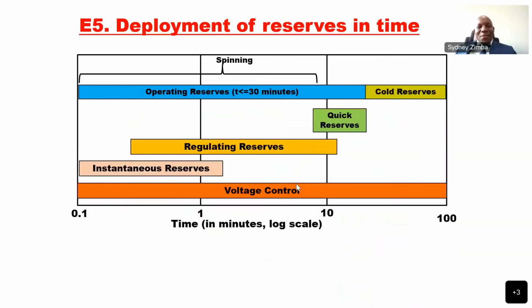So talking about the reserves, how are they deployed? In time, the instantaneous one is in milliseconds. An event happens quickly, we want to respond and correct the discrepancy. Then after milliseconds, close to a minute, the regulating reserves come in. At that time, the instantaneous reserves are released to get them set for the next disturbance. Then those quick reserves which are offline can now be synchronized. So all these up to quick reserves are operating reserves. Then going forward, after 10 minutes or so, we dispatch the cold reserves through market arrangements, or we run the generators which were offline.